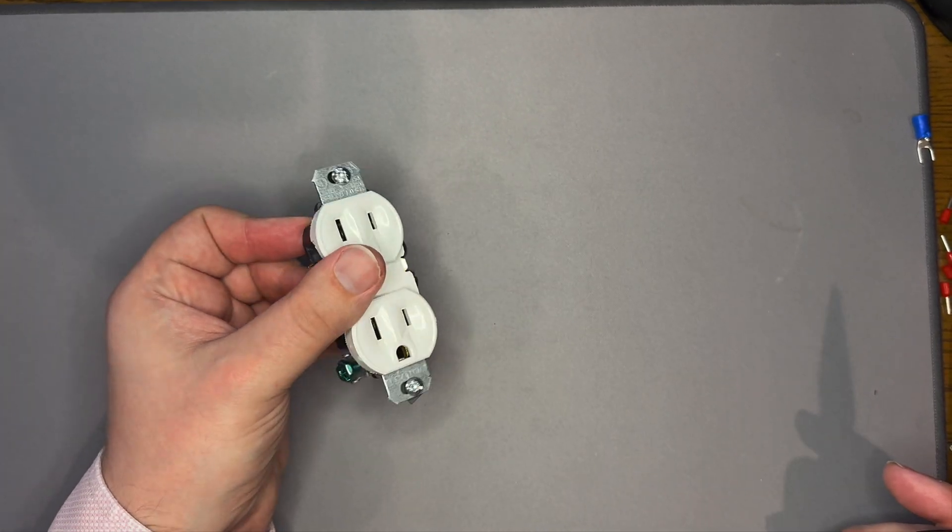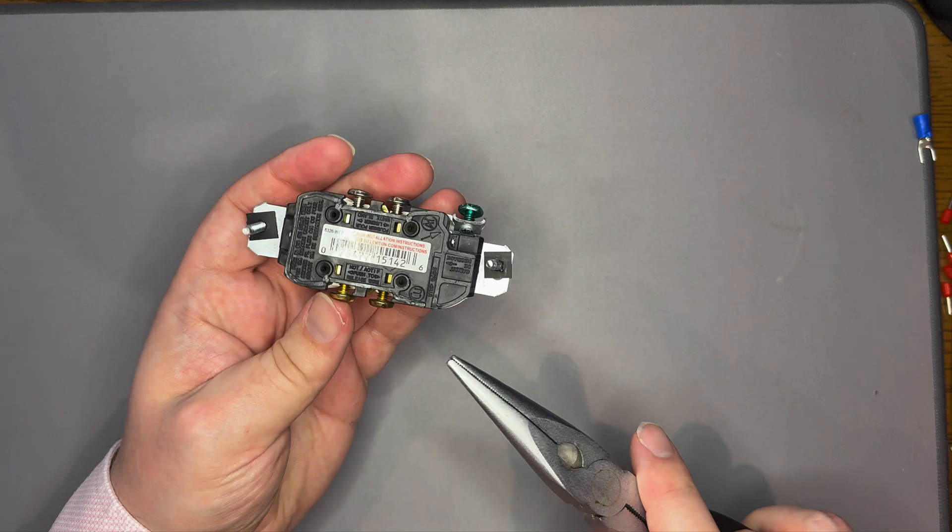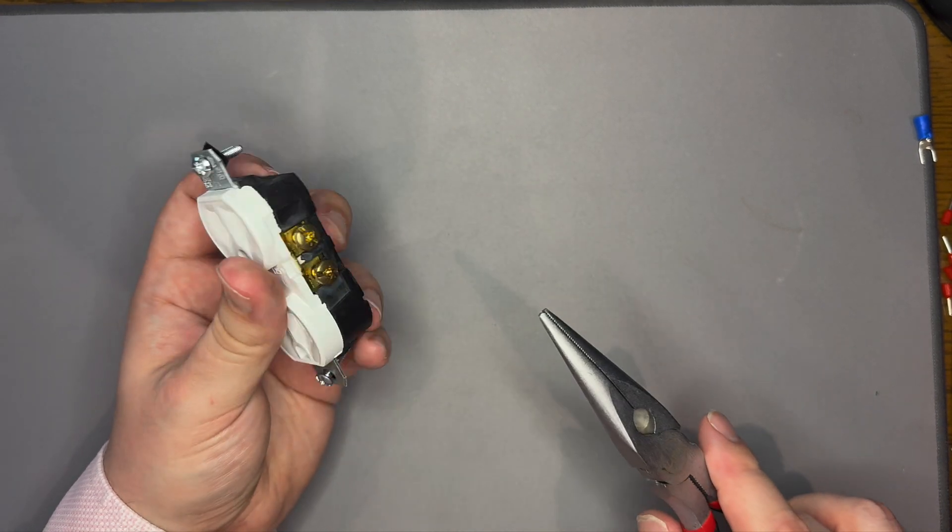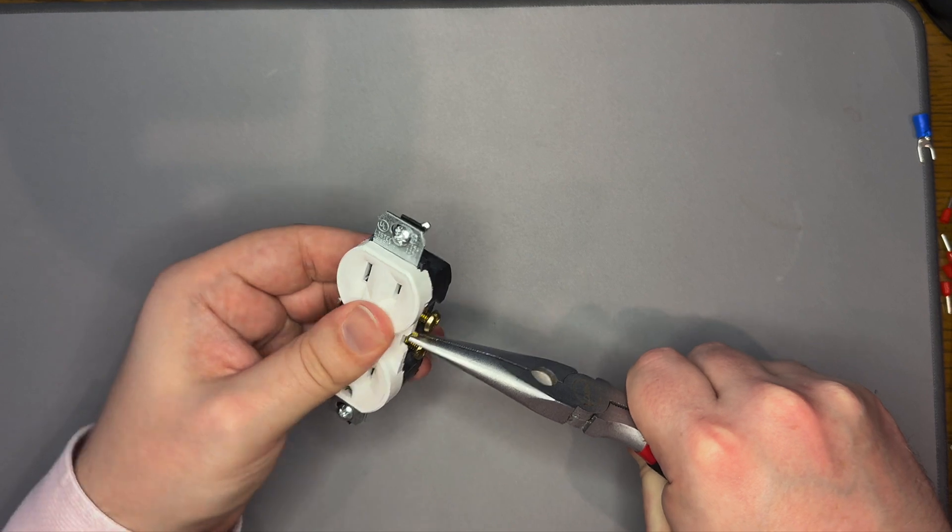Next, we will separate the hot terminals for the top and bottom outlet. The hot terminals, on the right side, are connected with a metal tab. Using pliers, grab this tab and bend until it breaks off.